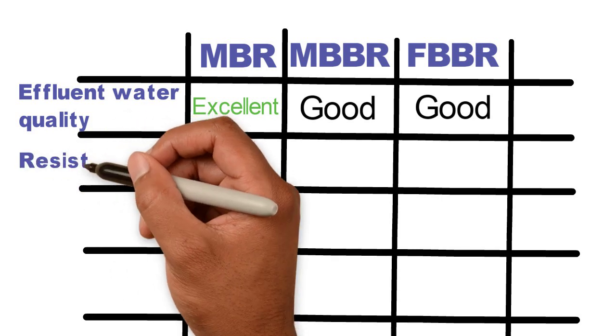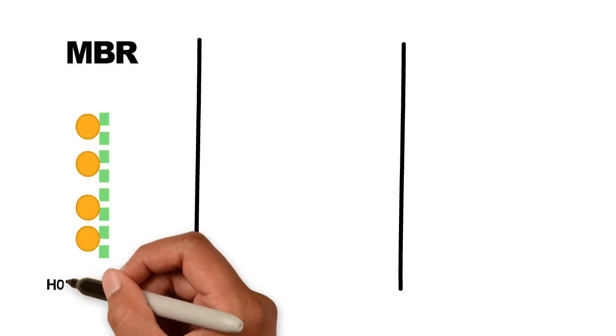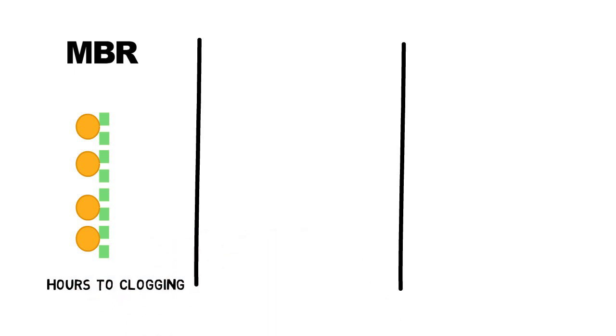Resistance to influent peaks and grease leaks. MBRs are very sensitive to changing influent values. Grease leaks can cause clogging of the fine membranes so that they must be cleaned or replaced.